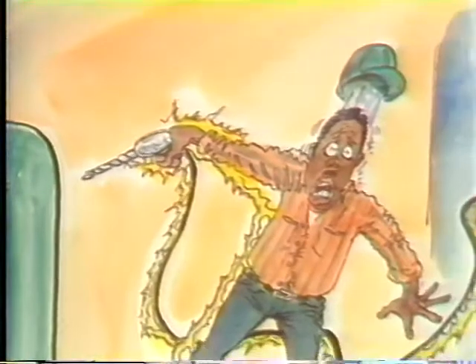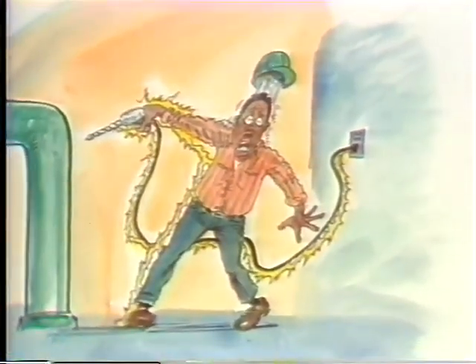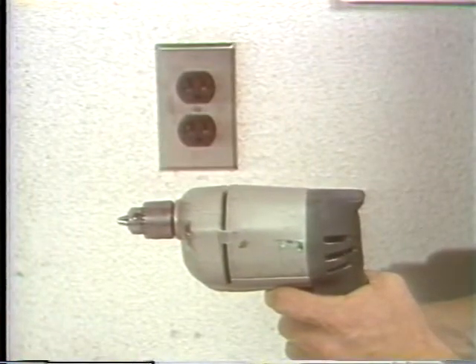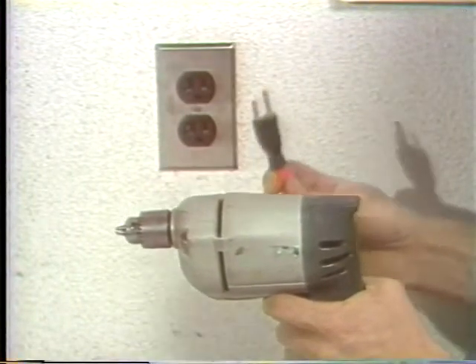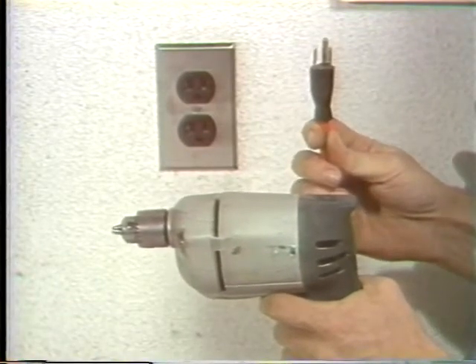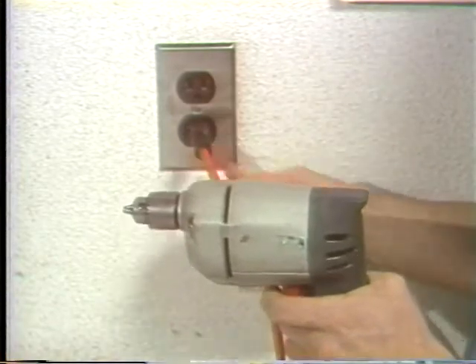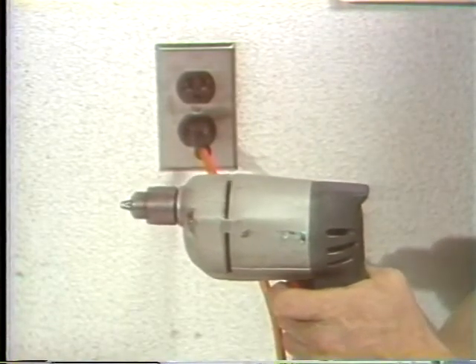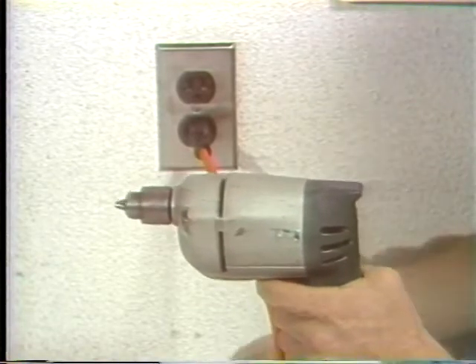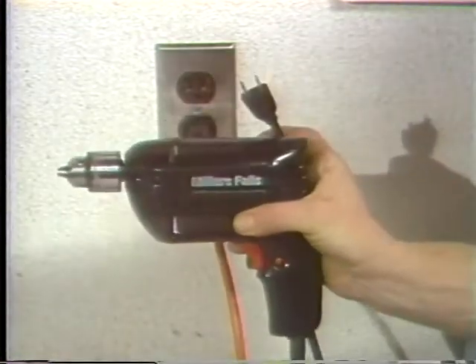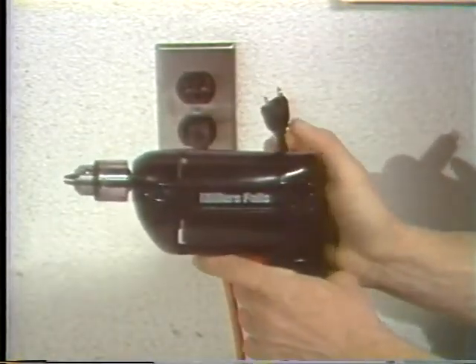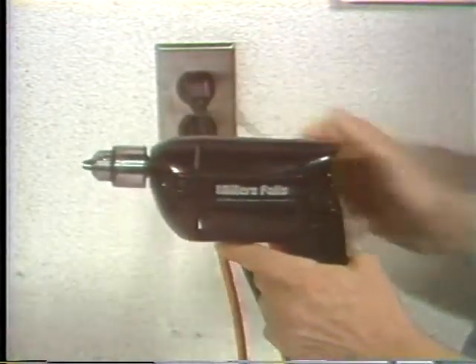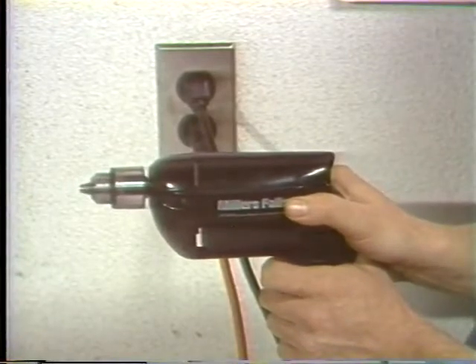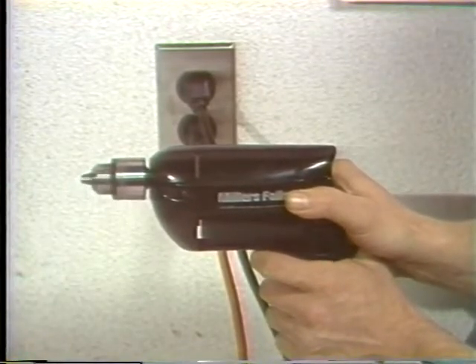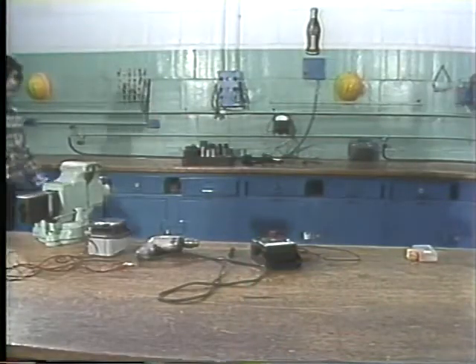Of course, portable electric tools also have to be grounded, and hopefully, if there's a fault, the shortest path to ground won't be you. Electric tools with metal casings should be equipped with a three-pronged plug like this one. The third conductor connects the casing to a grounded terminal in the receptacle, so stray current to the housing travels to ground without going through your body. On the other hand, double insulated tools don't have to have a ground conductor. They have plastic casings that insulate you from any fault inside the tool. If the casing's in good condition, there's very little chance of getting shocked. Grounded tools with metal casings are much more common, though, so let's see how they're inspected for safety.